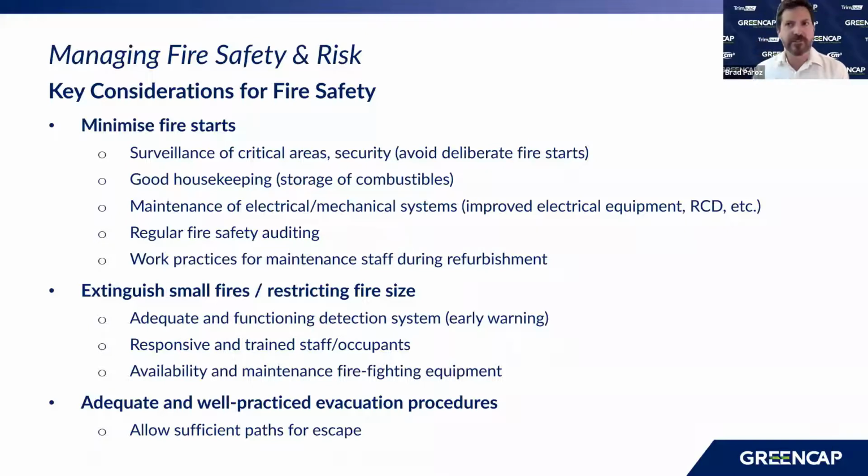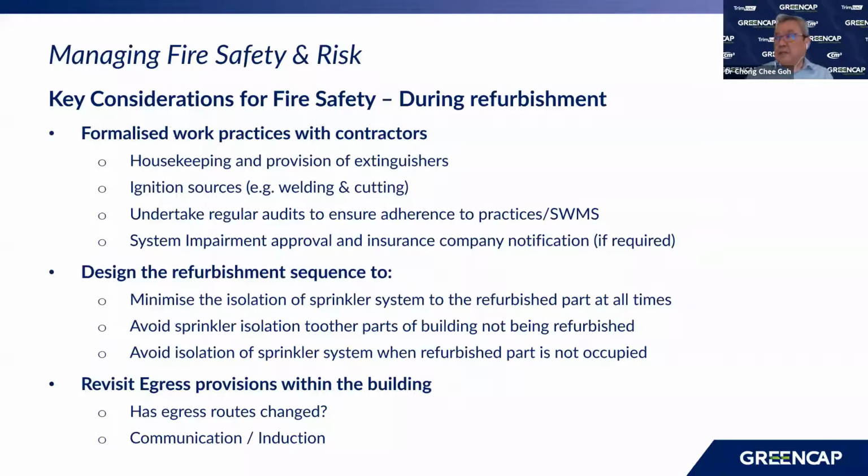Chong Chi, you referred to work practices for maintenance staff a little while ago. What do you mean by that? Can you flesh that out a bit? Yes, from time to time, we know that during refurbishment work, that's where the tendency of a fire starting is. Other than the electrical and mechanical components, during refurbishment that's when you do a lot of hot work and so forth. So the whole idea of building refurbishment is to make sure that we have formalized work practices for contractors.